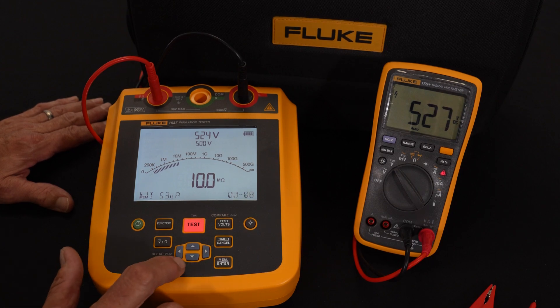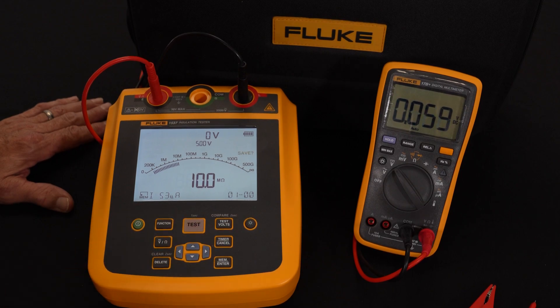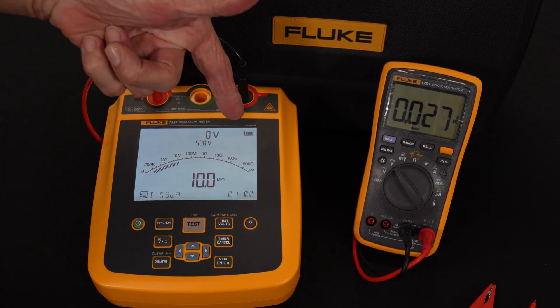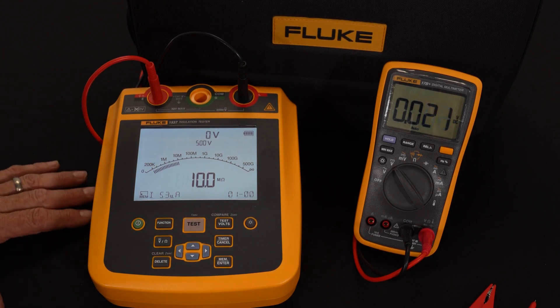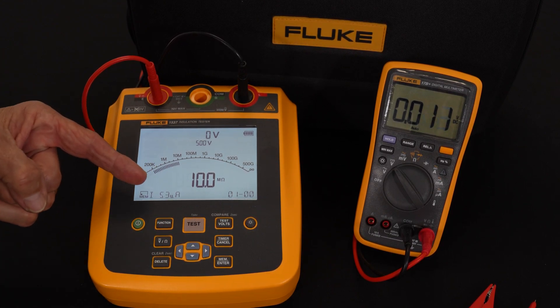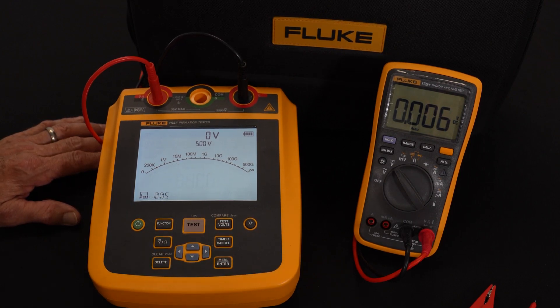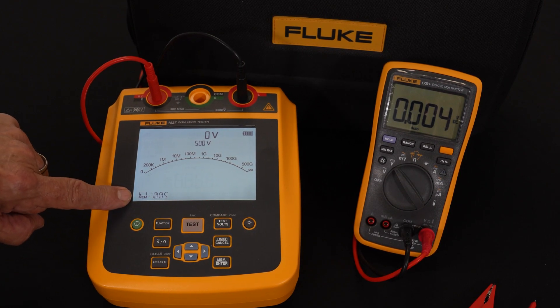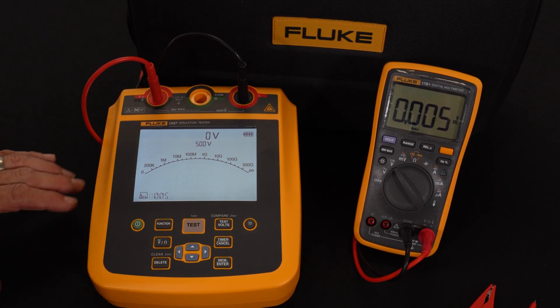The test is running through and we've come to 60 seconds. I'm going to hit the stop button right now. The instrument will now ask me if I want to save, with a question mark. The actual reading is being held on the display. The leakage current, which right now is showing 53 nanoamps — that's extremely low — is all there.